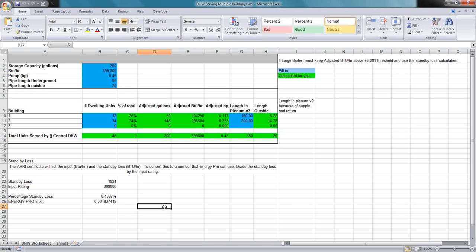Another question was, what happens when the existing water heater is so old that it's not listed in the CEC or AHRI directories? There are tables available in Title 24 called the vintage tables. They're also sometimes referred to as default values. They're also referenced in our energy modeling guidelines and the contractor and rater handbook of the multifamily upgrade program.